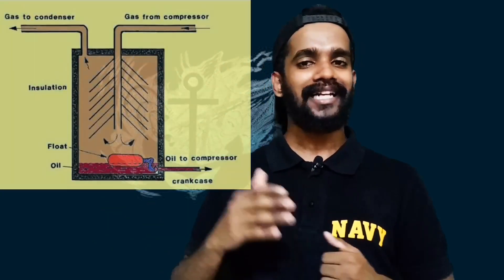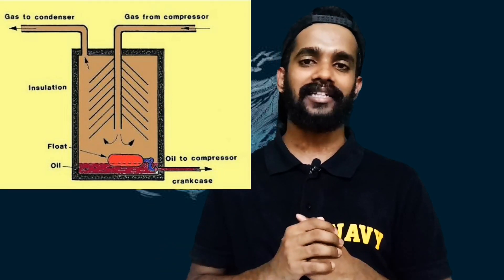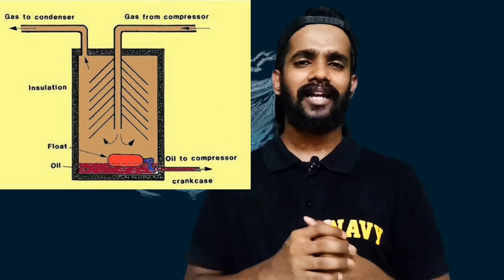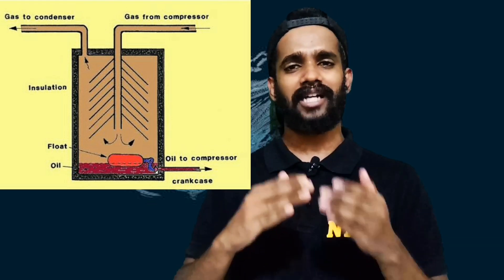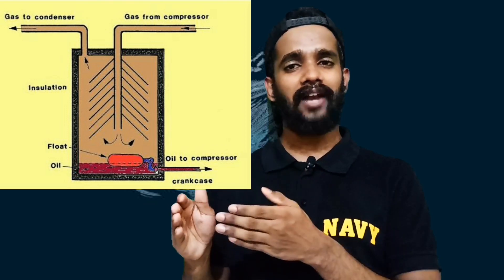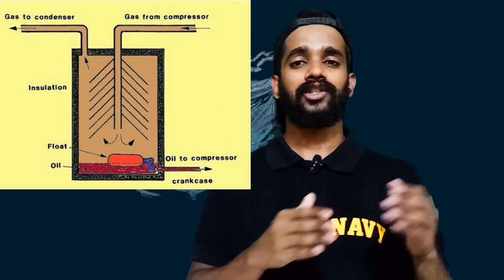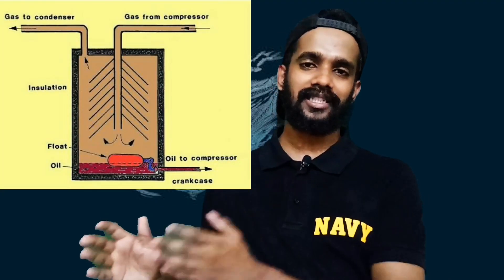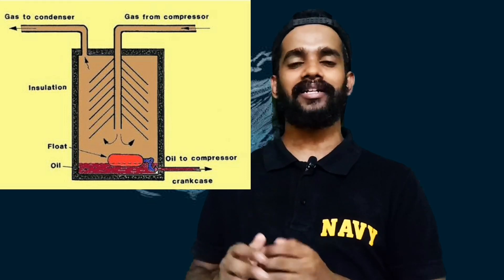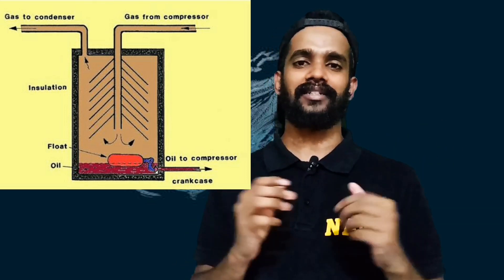Whatever oil is present at the bottom of the oil separator will be carried back to the compressor crankcase. As is clear from the diagram, upon reaching a certain level, the float will be raised upwards. As the float raises, the valve will be opened and the path becomes clear so that the oil goes back to the compressor crankcase. The oil goes back to the compressor crankcase via the float and valve arrangement, and the refrigerant gas goes to the condenser for condensing.